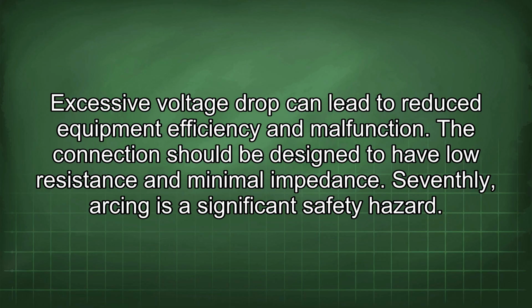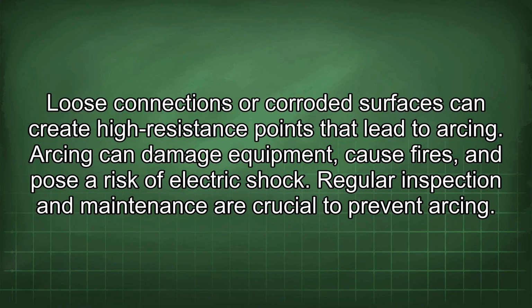Seventhly, arcing is a significant safety hazard. Loose connections or corroded surfaces can create high resistance points that lead to arcing. Arcing can damage equipment, cause fires, and pose a risk of electric shock. Regular inspection and maintenance are crucial to prevent arcing.